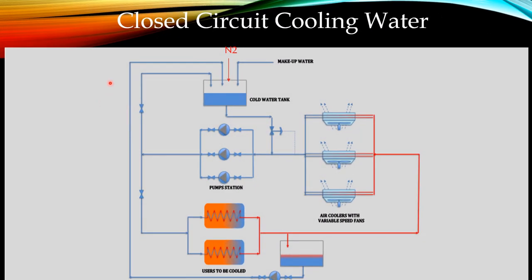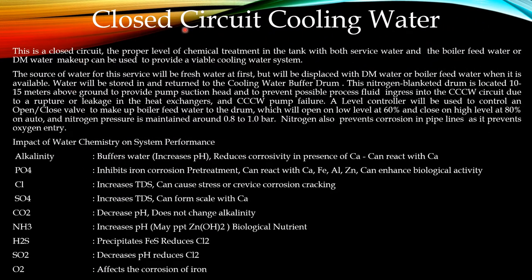In this episode we will see about the closed circuit cooling water. This is a schematic diagram of a closed circuit cooling water system. The buffer tank or storage tank is given with nitrogen blanketing. Makeup water — normally demineralized water or boiler feed water — is provided. Service water makeup is also available, and this is the pump section, which goes to a heat exchanger to pick up the heat load. One portion then circulates back and another goes to the cooling area where air coolers cool the hot water before returning to the pump section.